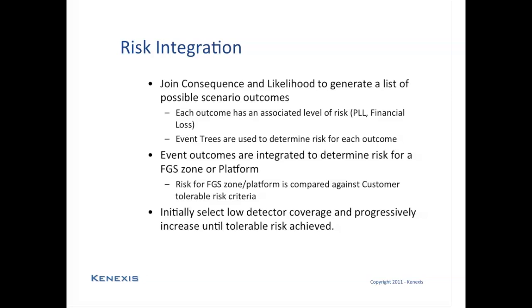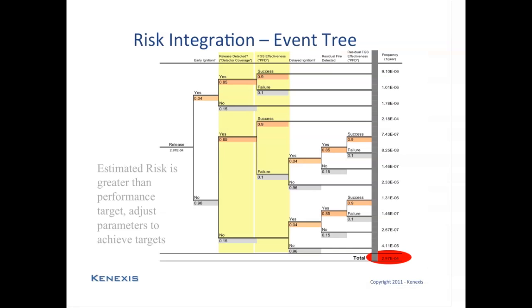Initially, this process is done by selecting a low detector coverage and then progressively increasing the number of detectors and the safety availability of the safety instrumented system until the tolerable risk target has been achieved. This is going to occur in a recursive fashion. Now, understanding how the risk integration works and how detector coverage and fire and gas system effectiveness are incorporated into the overall risk analysis, what needs to be done is to consider the detector coverage and the fire and gas system effectiveness, as shown in the risk integration event tree below.